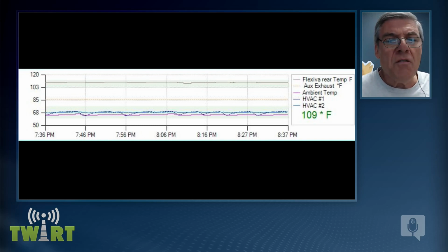I always strive to have the room temperature right. I used to have air conditioning maintenance people ask what I wanted in the room, and I put it in terms of the equipment being just like humans. Humans don't want 90 degrees, and the equipment doesn't either. We can probably suffice in both cases, but when you're looking at a 40-degree spread and 109 degrees on the output, if you're only starting at 85 or 90 degrees in the room, you're not starting at a good place to end up for the transmitter.